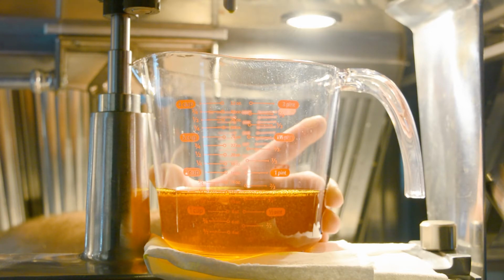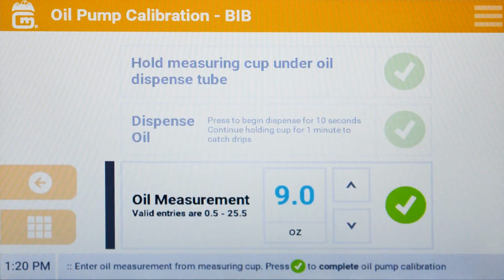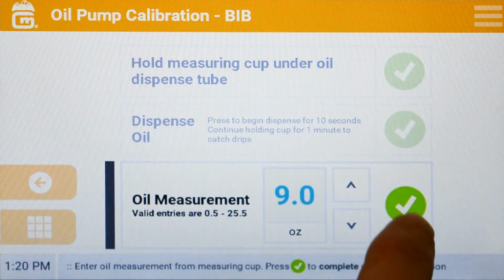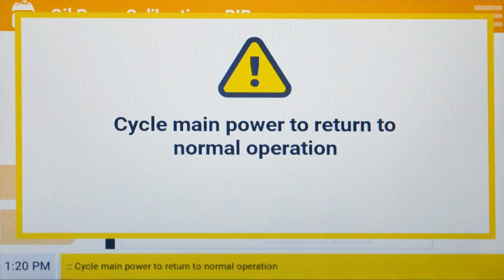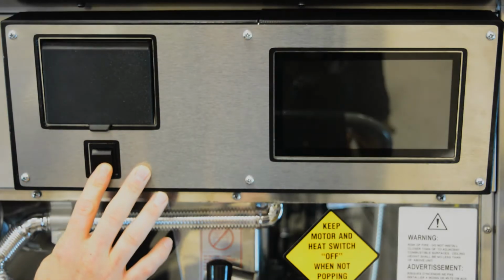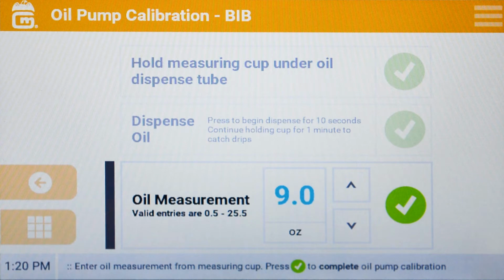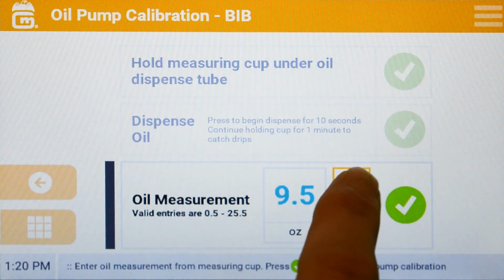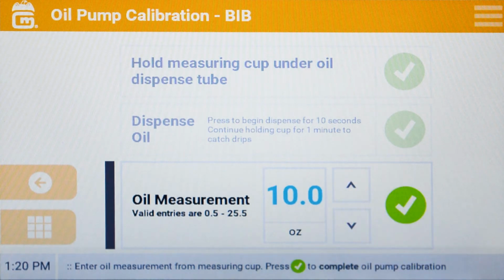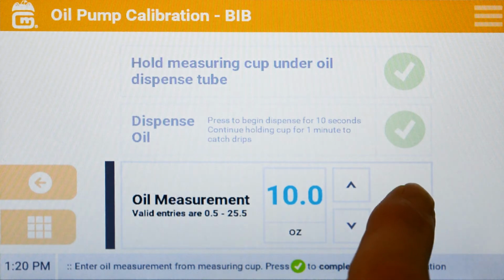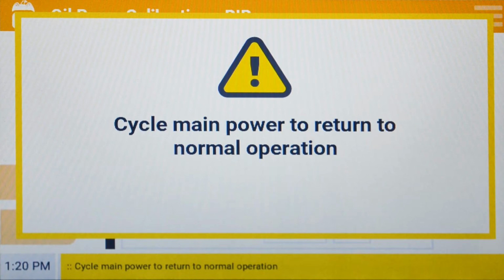After the pump is finished, compare the oil measurements to the volume shown on the screen. If the oil amount shown on the screen matches what is in the measuring cup, press OK and turn off the unit. If the oil volume does not match, press the up arrow to increase the oil volume, or press the down arrow to decrease the oil volume. Once the volumes match, press OK and turn off the unit.